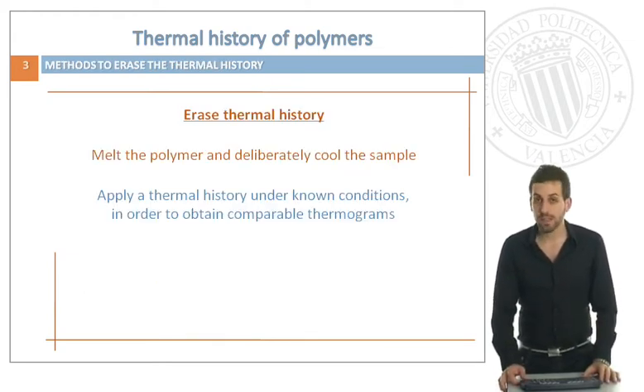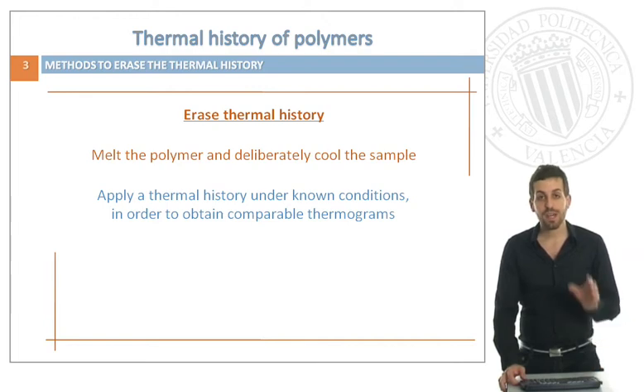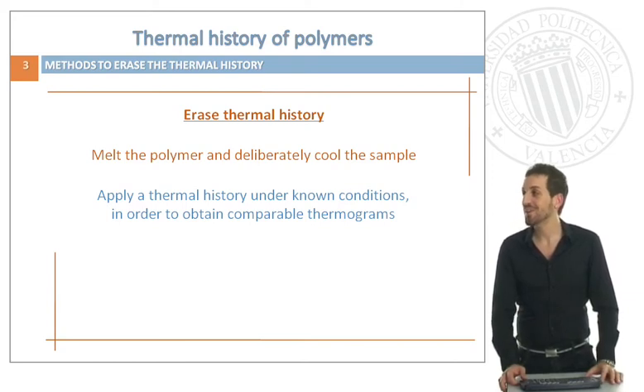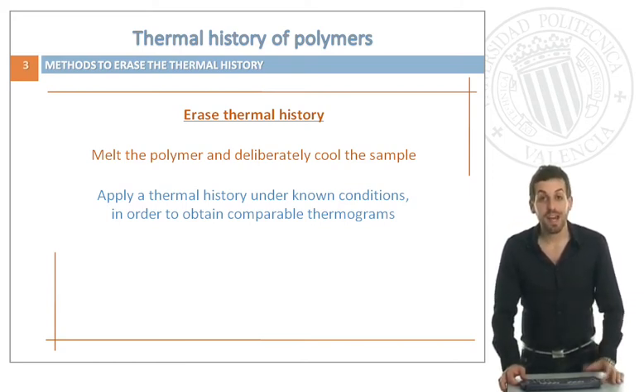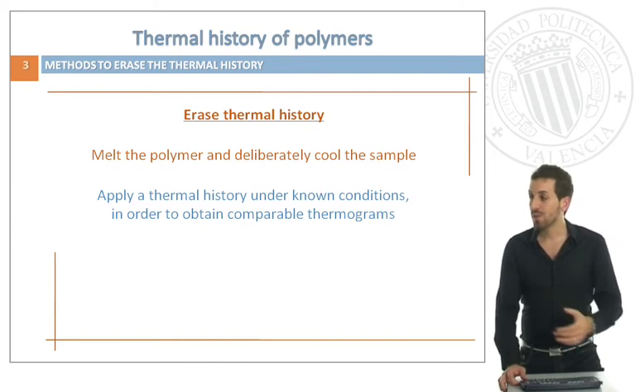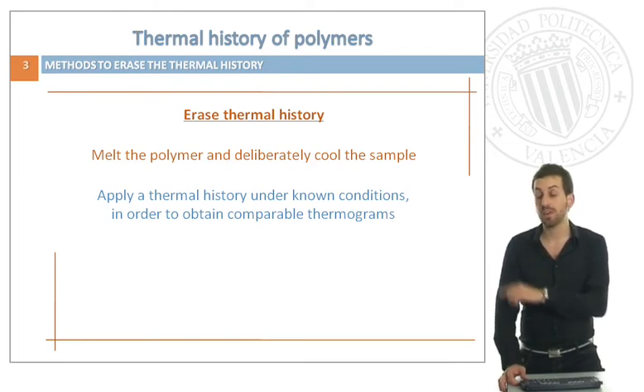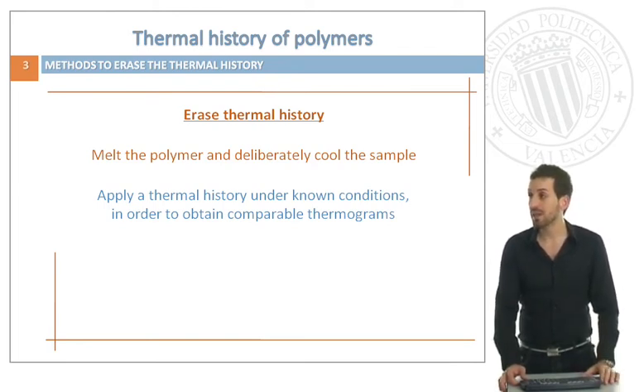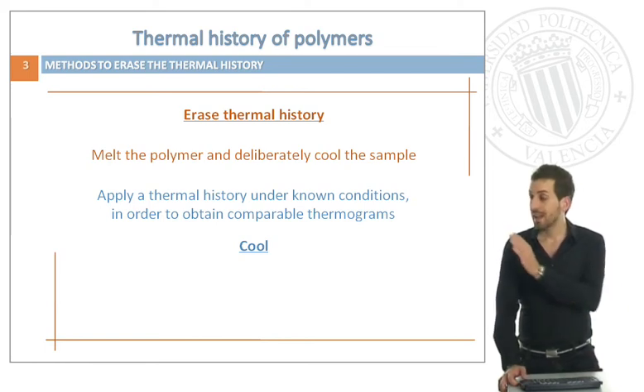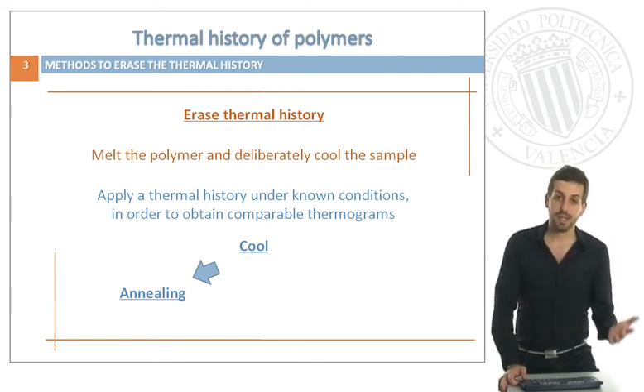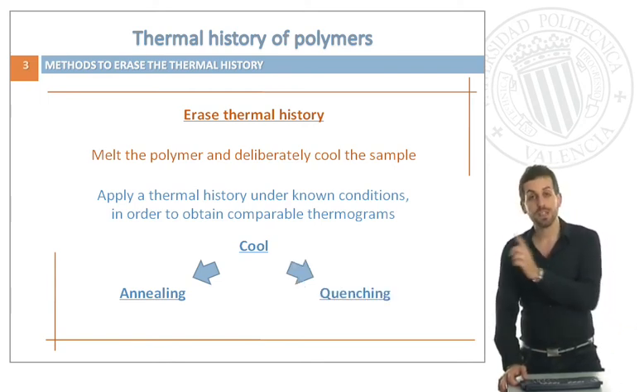If we are not interested in them we have to erase this thermal history. How can we do that? We have to first melt the polymer and deliberately cool the sample, that means apply a known and specific cooling scan. Then we will apply this thermal history under known conditions — this is the cooling I was referring to — in order to obtain comparable thermograms. This can be done by different methods: we can anneal or quench, as we will see.